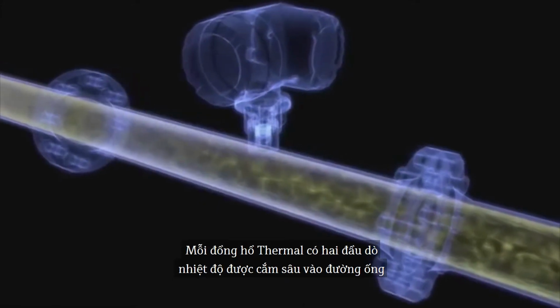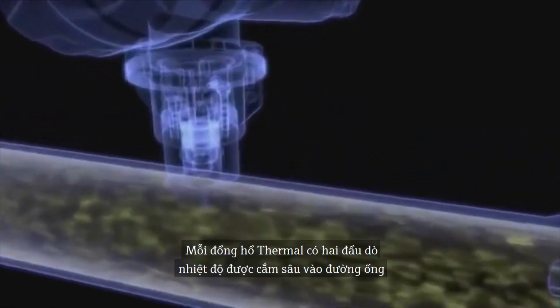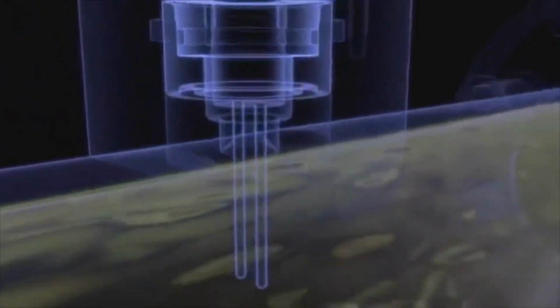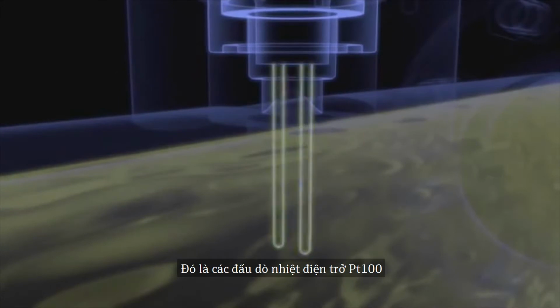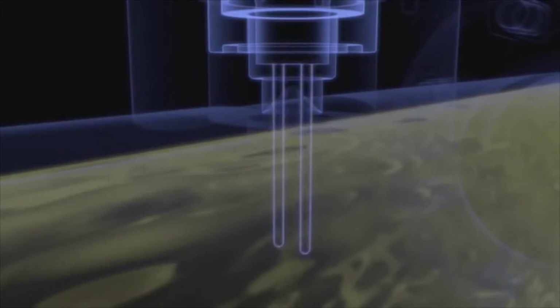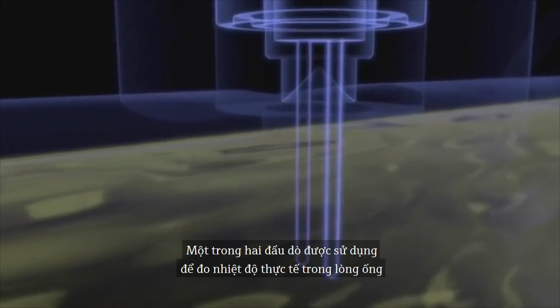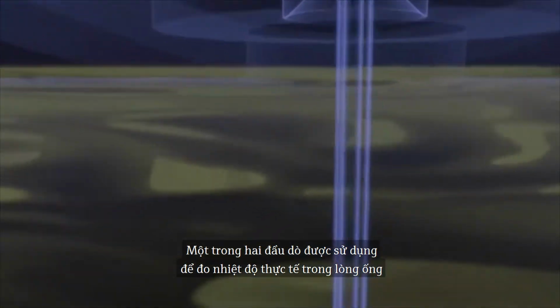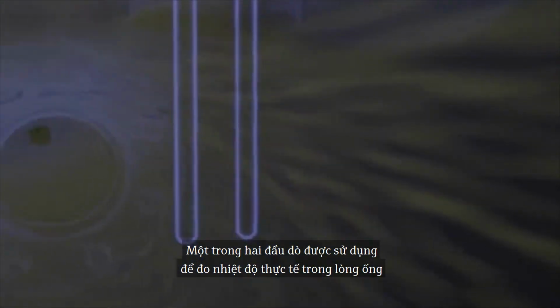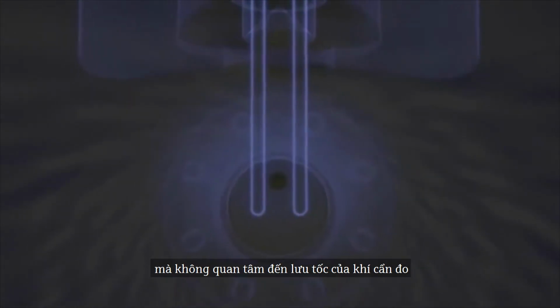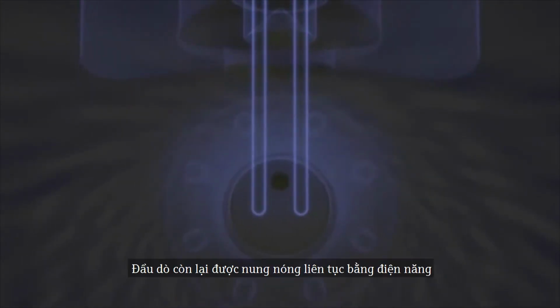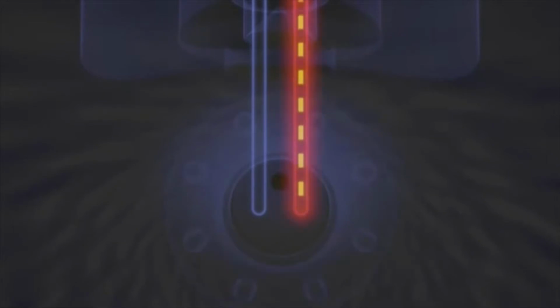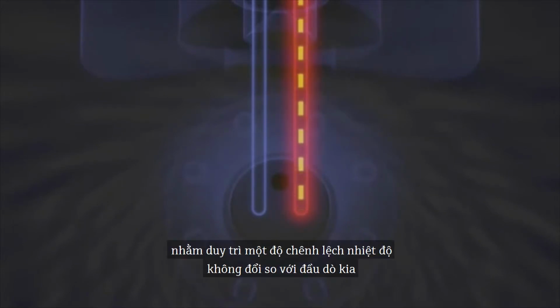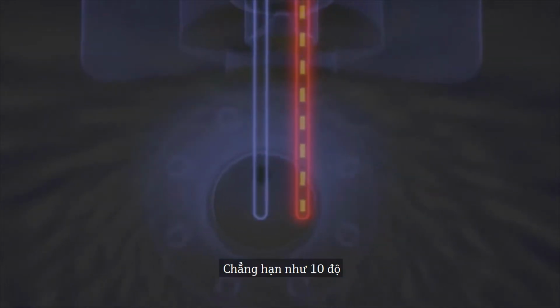Inside thermal flow meters are two temperature sensors protruding into the measuring tube. They're known as PT100 resistance thermometers. One of these temperature sensors measures the actual gas temperature as a reference, regardless of the flow velocity. The second temperature sensor is heated constantly via electrical energy, so that a predefined temperature difference is maintained between the two sensors. For example, 10 degrees.